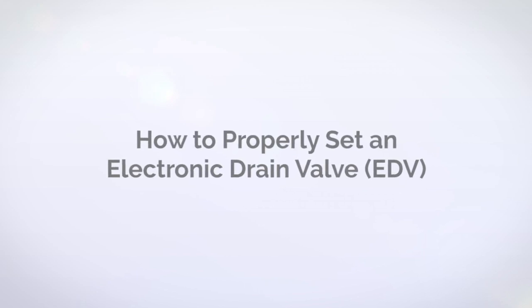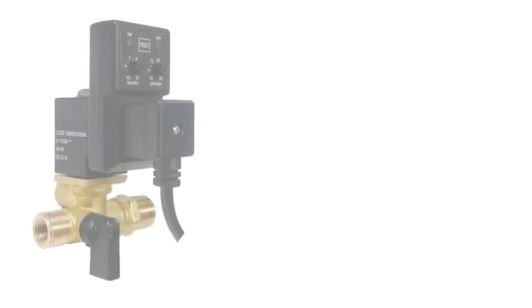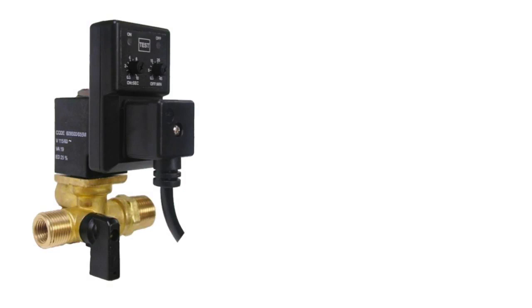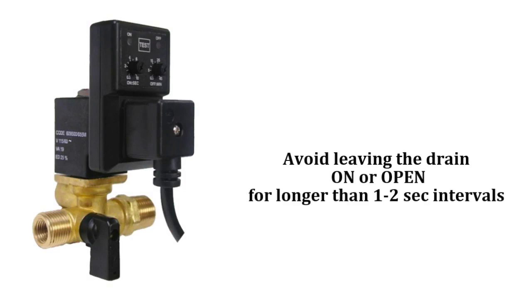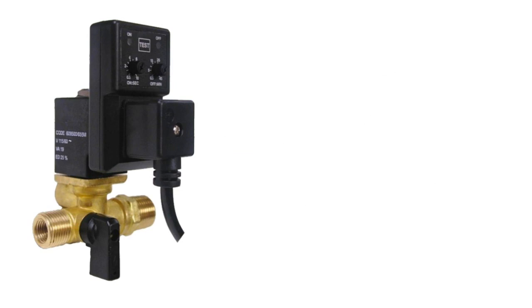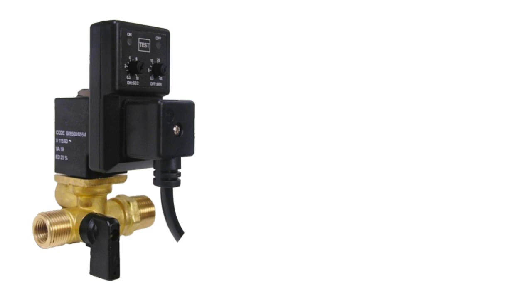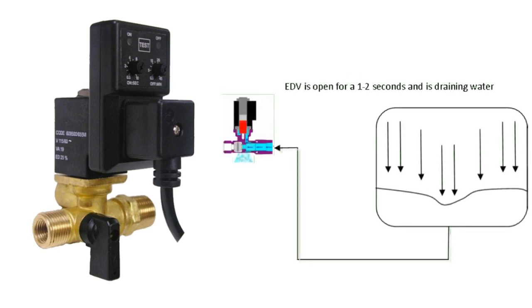One of the most common mistakes we see in pneumatics is improper setting of the timer control on the electronic drain valves, or EDVs. When setting your EDV, avoid leaving the drain valve on or open for longer than one to two second intervals. Remember, air will travel through the path of least resistance. If a drain valve remains open for longer than two seconds, air forces liquid to the side of the port, resulting in only a light mist being expelled from the EDV. Now the drain has become less effective, and the wasted purge creates a less efficient air system.